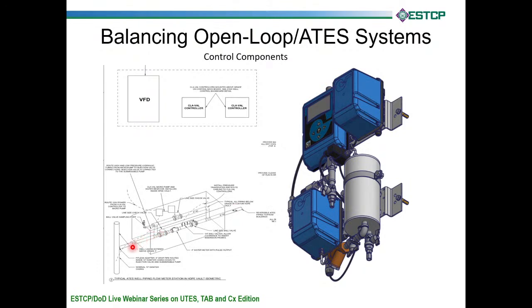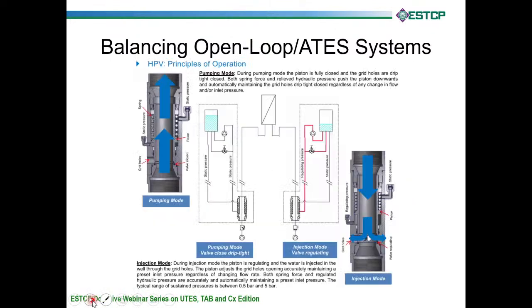We also have a water level transmitter that goes down the well and is connected all the way back up to the controller, so we know the level in the well. So this device allows us to control our injection valve, and I'll show you what we do with that. Here's our injection valve that is down in the well. The pump will be sitting down here. The injection valve screws right onto the top of the pump.